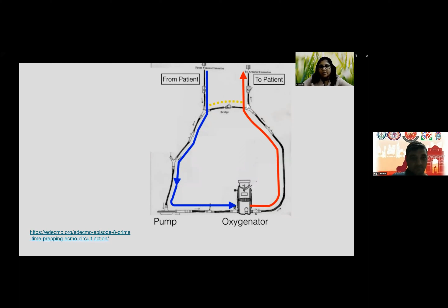So understanding the technical data about the PLS system, the total priming volume needed is around 585 ml. The blood flow rate is 0.5 to 7 liters per minute, and the gas exchange surface area of this oxygenator is around 1.8 meters squared. The heat exchange surface area is around 0.4 meters squared, and this is the water connector, the housing material, the fiber material for the gas exchange, and the fiber material for the water flow. And the centrifugal pump has a surface of around 190 centimeters squared. It is made up of polycarbonate.